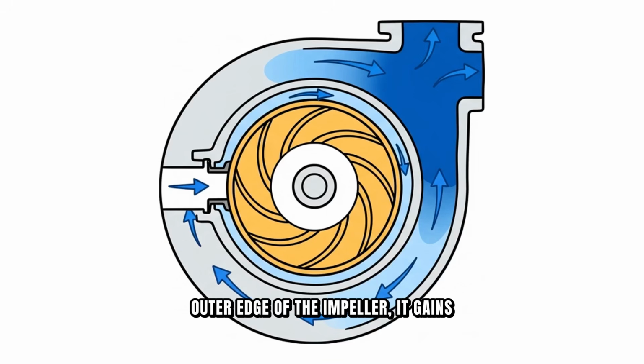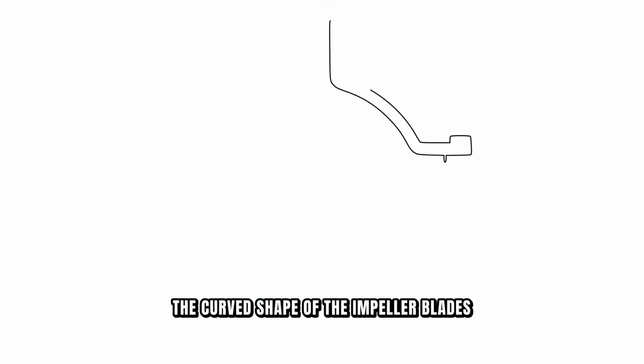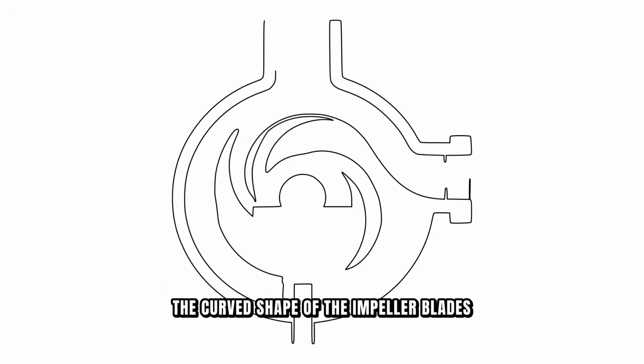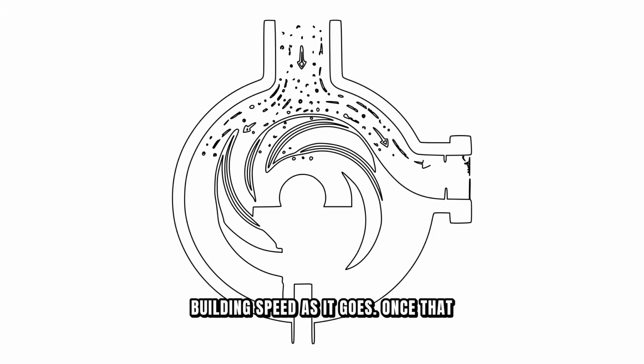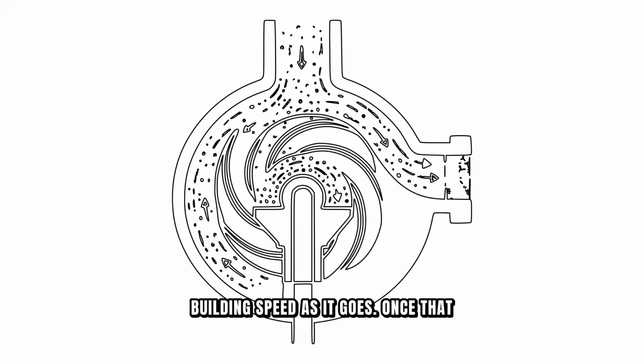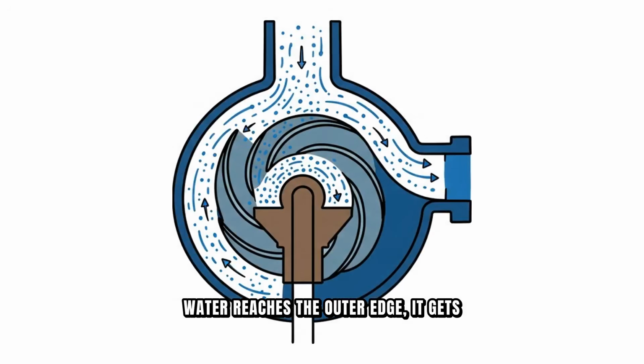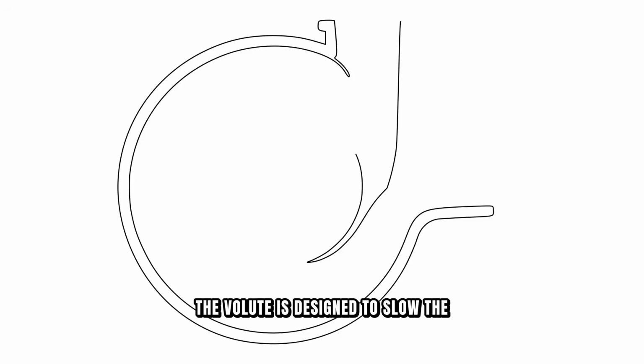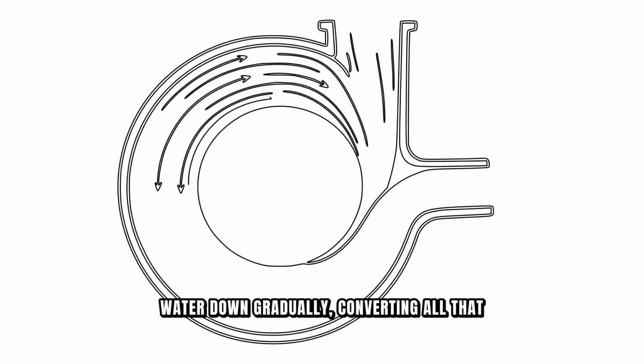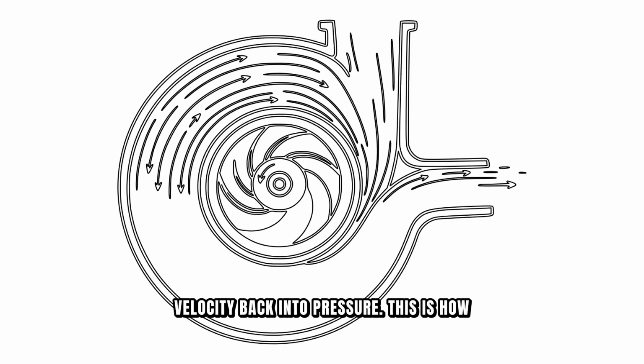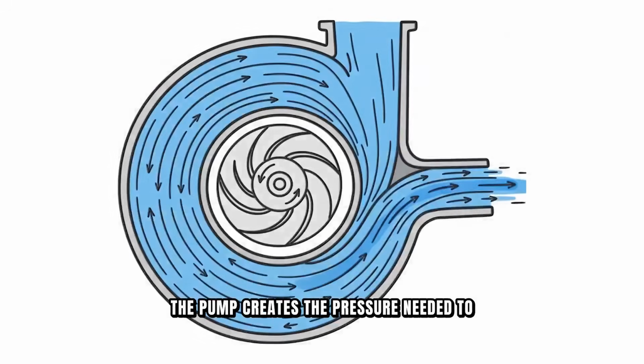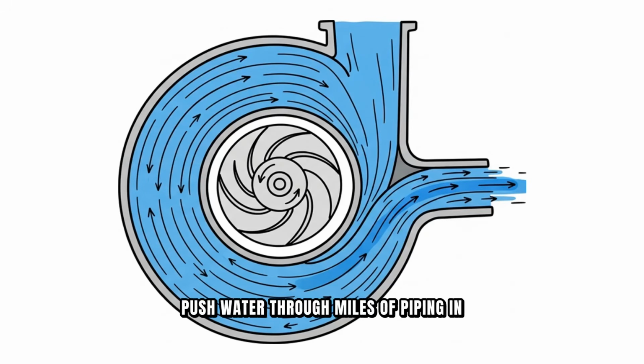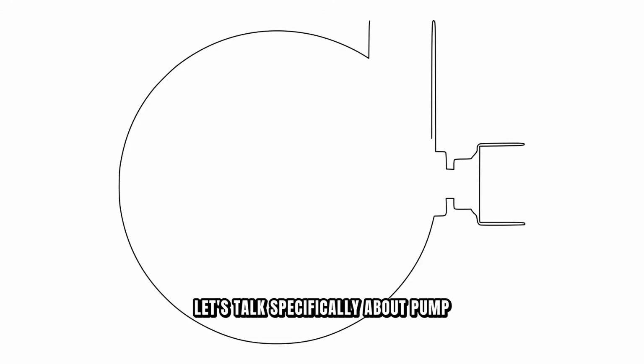As water moves from the center toward the outer edge of the impeller, it gains velocity and pressure. The curved shape of the impeller blades guides the water in a spiral path, building speed as it goes. Once that water reaches the outer edge, it gets forced into a specially shaped chamber called the volute. The volute is designed to slow the water down gradually, converting all that velocity back into pressure. This is how the pump creates the pressure needed to push water through miles of piping in a building.